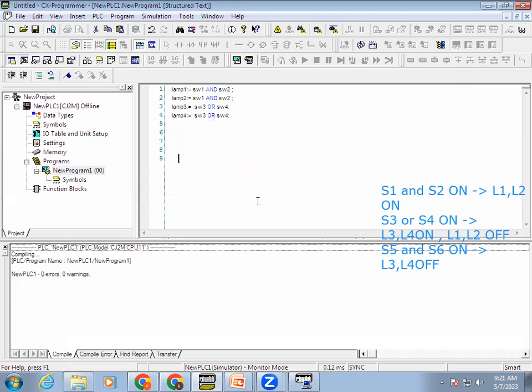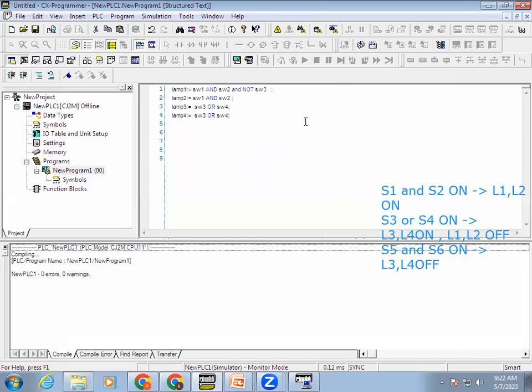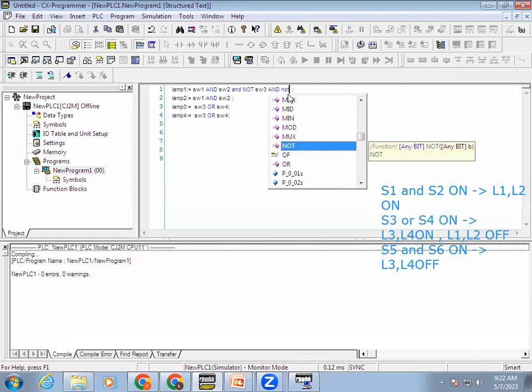Now the ON condition is done, so now we have to give the OFF condition. When Lamp 1 and 2 should be off — when SW3 or SW4, if either one is activated, L1 should be off. What we have to do is give AND. In ST, for the NC contact, we use NOT — so NOT SW3 AND. Think about what you do in LD: in LD we connect the NC contact in series — Switch 3 and Switch 4. So in here, either one activating makes L1 and L2 go off, so we connect the NC contact in series, that's why we give AND NOT SW3 AND NOT SW4.